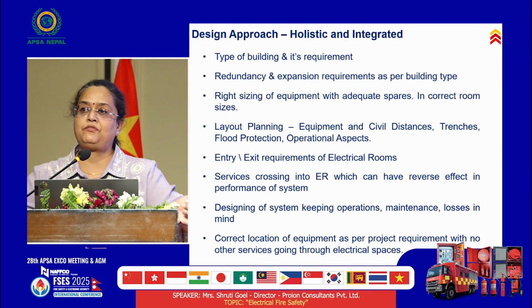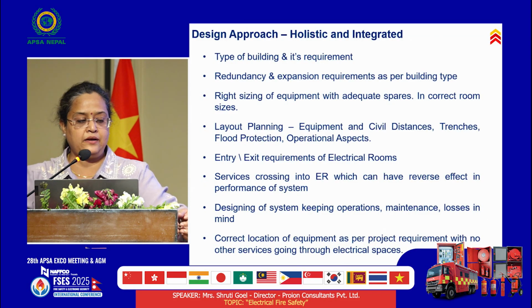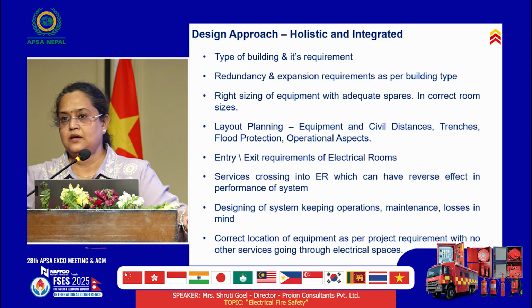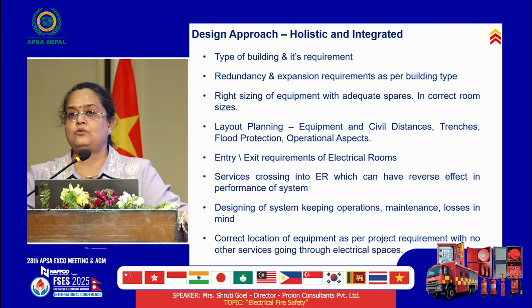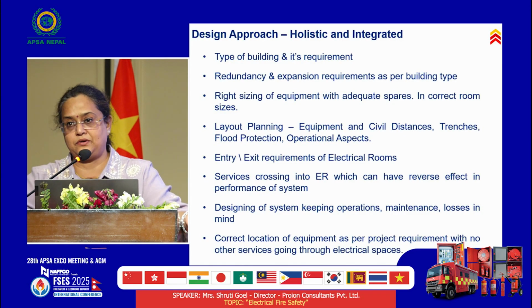So if I'm designing a building's electrical system for 25 years, for the next upcoming 25 years the technology of the systems is going to change, the watt per square foot requirement is going to change. So my high side system should be designed in a way that it's able to sustain the load without undersizing the equipment for the next 25 years.